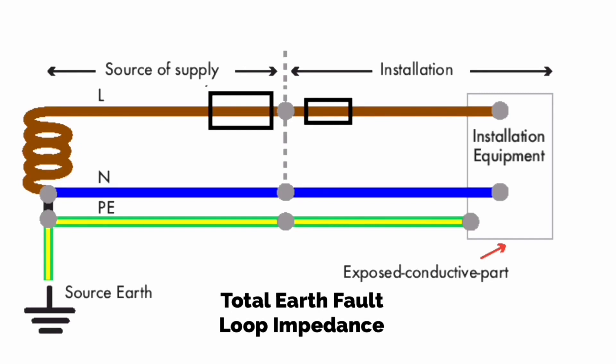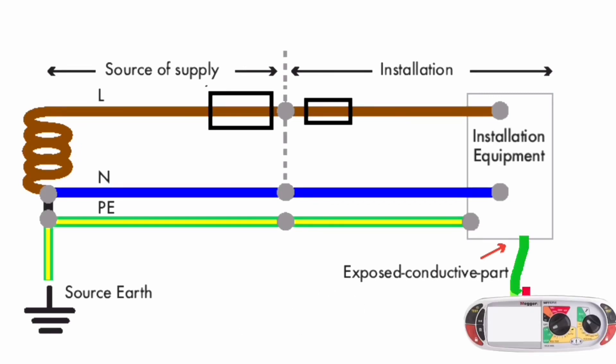Total earth fault loop impedance ZS is measured at the furthest point of a radial circuit and comprises the impedance offered by the line conductor R1, the impedance offered by the circuit protective conductor R2, and the impedance offered by the supply authority's cable.